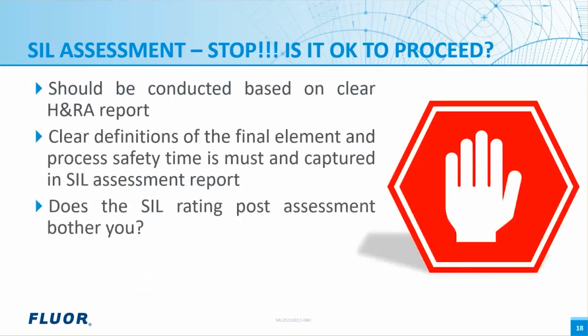So moving on, post hazard and risk analysis, the next important phase is SIL assessment. Many times, SIL assessment studies are conducted back to back or integrated with HAZOP. This means that a clear HAZOP report is not available. Incomplete HAZOP could mean inadequate understanding of the scenarios for the SIS. Is it a good practice? Definitely not. It may result in missed requirements or higher requirements on the SIS.